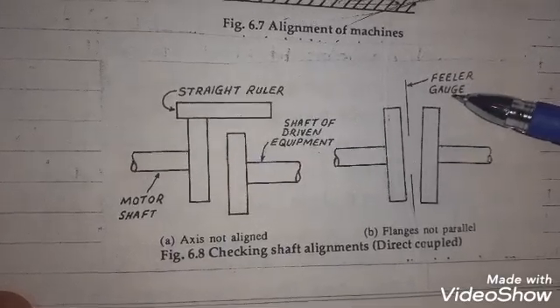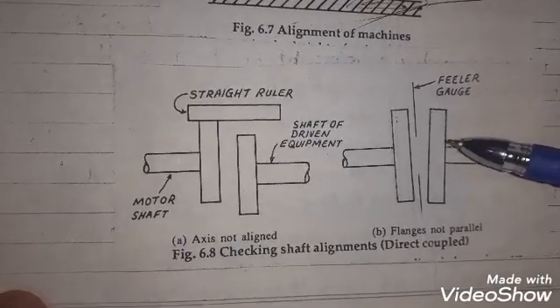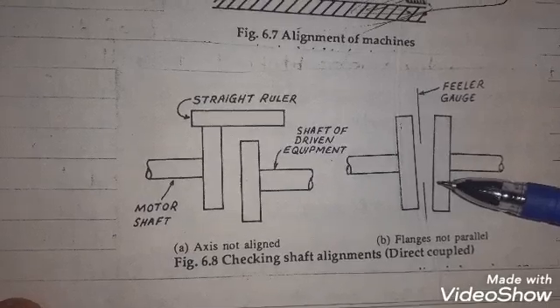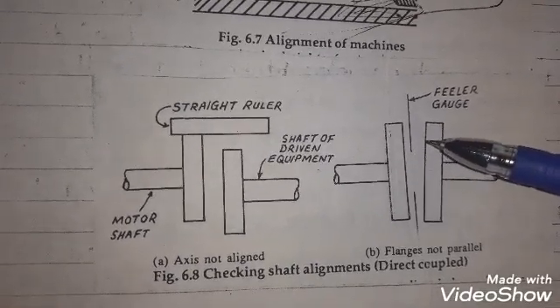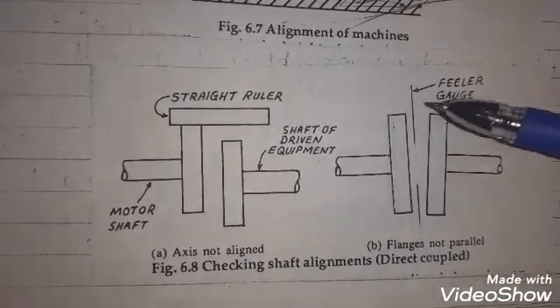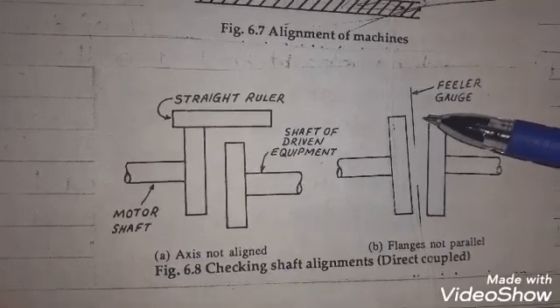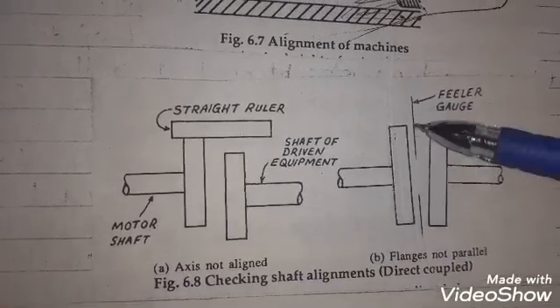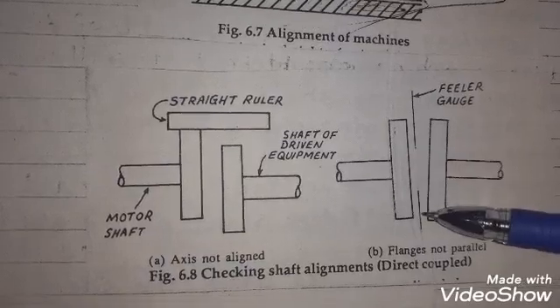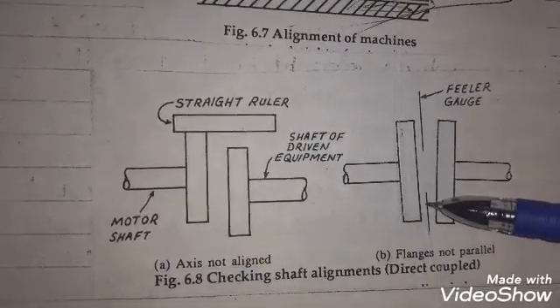For that we have to use the feeler gauge. Feeler gauges are made from steel ruler-like material, having 0.5 mm to 2 mm thickness. Put that feeler gauge inside the gap between these two flanges. If it goes throughout the length easily, indicating that the flanges are parallel.